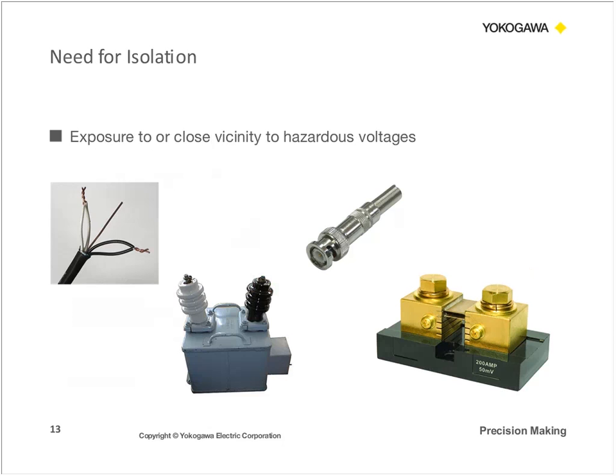So for industrial environments, this is fairly common. If you're working with exposed wiring or if you're connecting systems with metal contacts, such as BNC connectors or BNC alligator clips, or if you are working with potential transformers, current transformers, or any shunts that really deal with or have these metal contacts, you should consider isolation as a means to protect not only the user, but also the surrounding equipment from potential hazardous voltages such as arcing, for example.